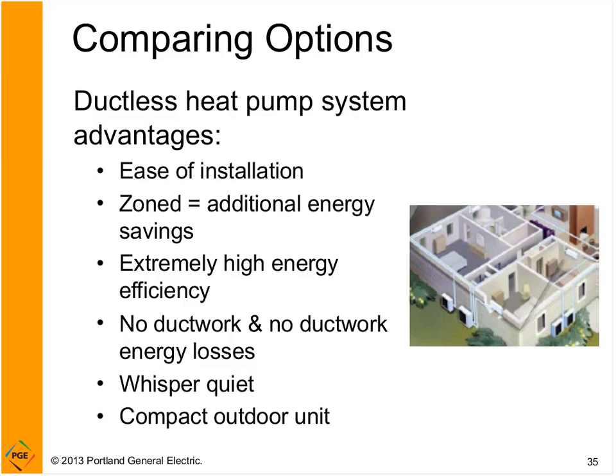Extremely high energy efficiency compared to ducted systems. No ductwork and no ductwork energy losses. So it's pretty common, a common number might be 20%, that you lose right off the bat through ductwork that's eliminated with a ductless system. Of course, they're going to be very quiet and a much more compact outdoor unit. So typically, the unit is going to be about the size of a large suitcase, let's say. I know it's maybe hard to tell the perspective from some of the pictures, but basically that's what the size is, a large suitcase.